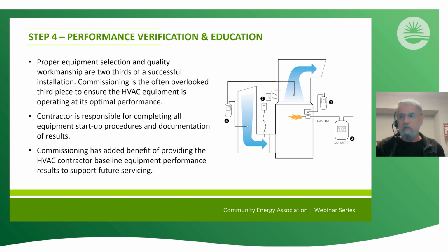What's the airflow coming out of the registers? What's the overall external static pressure? These are all terminologies that I can see people's eyes probably going sideways, going, what the hell is he talking about? You don't need to know all that. What you need to know is that needs to be measured, and not only measured, but documented. It also gives you a chance to see, when you're measuring all these things, if something's out. You go, wait a minute, this is not within range. And then you can discover why and resolve it. So it's not rocket science. Anything can be resolved. It gives you an opportunity to do that.